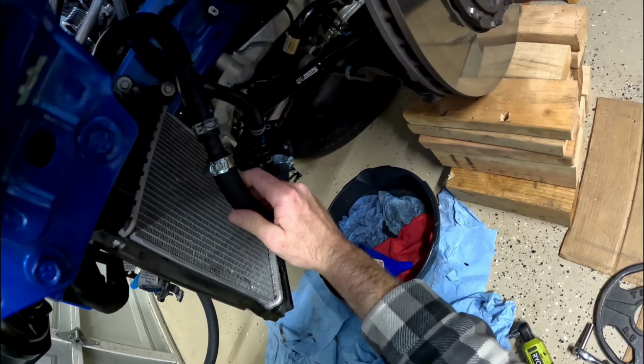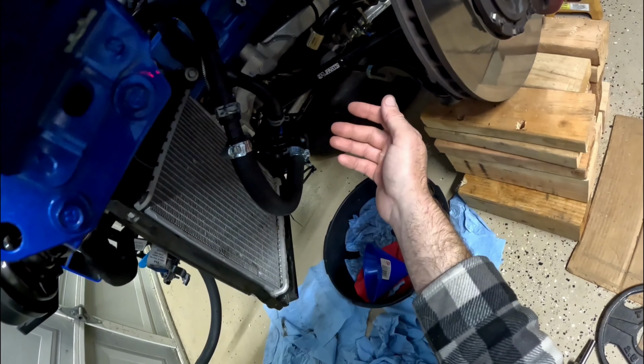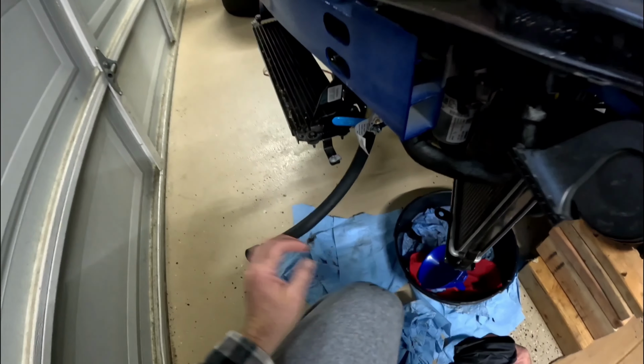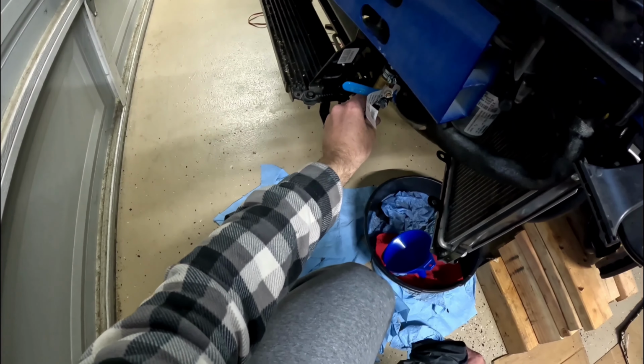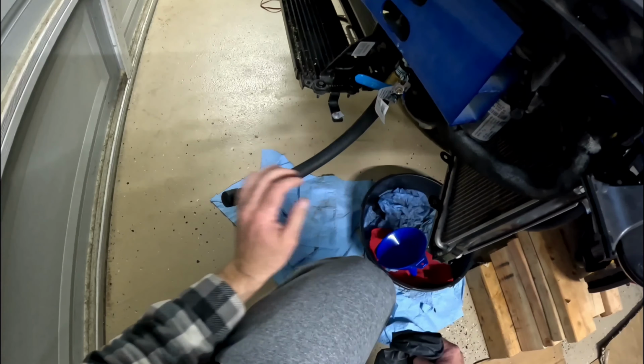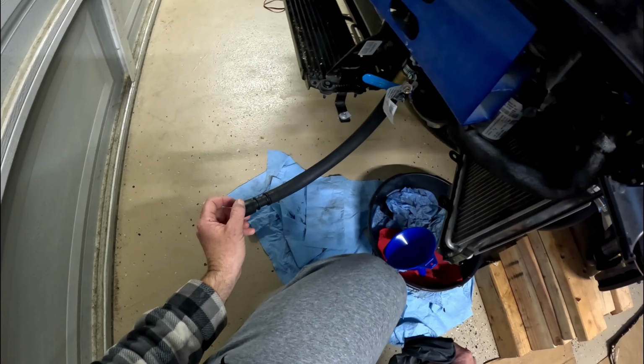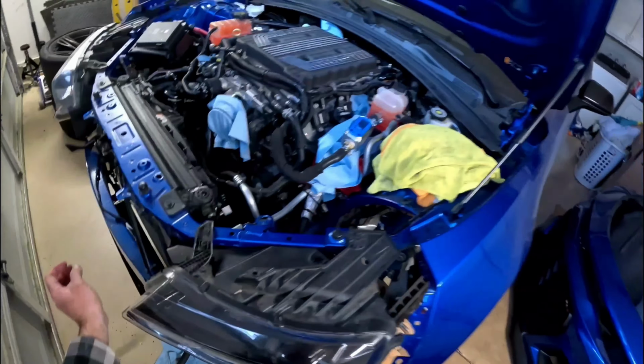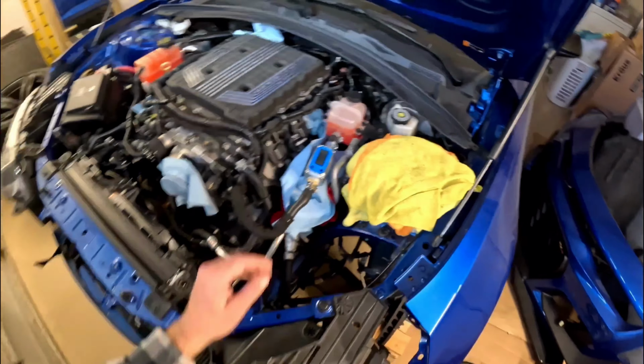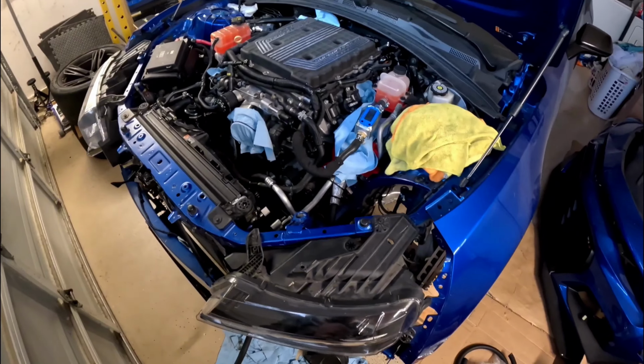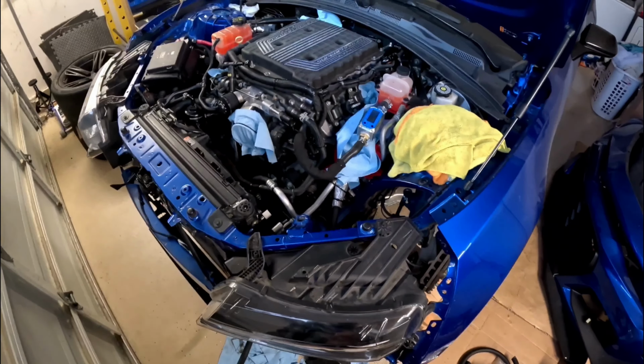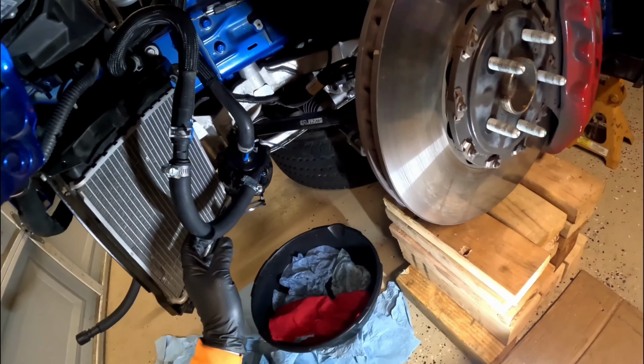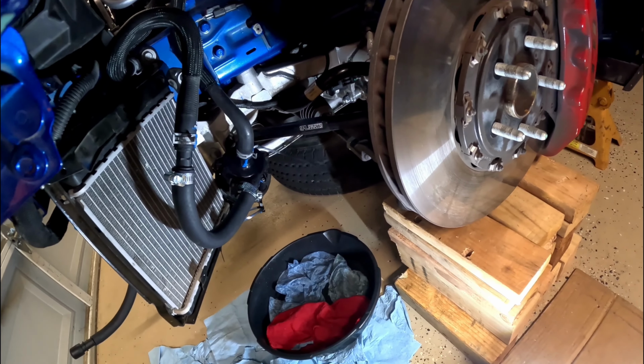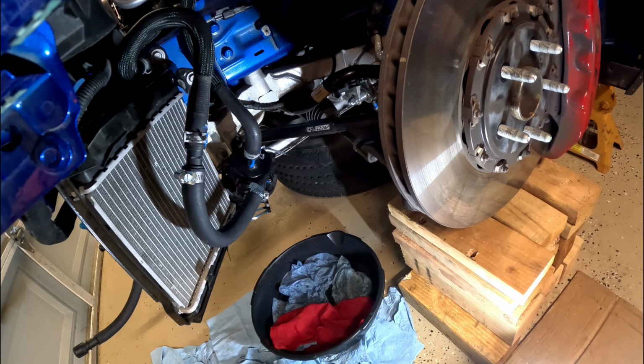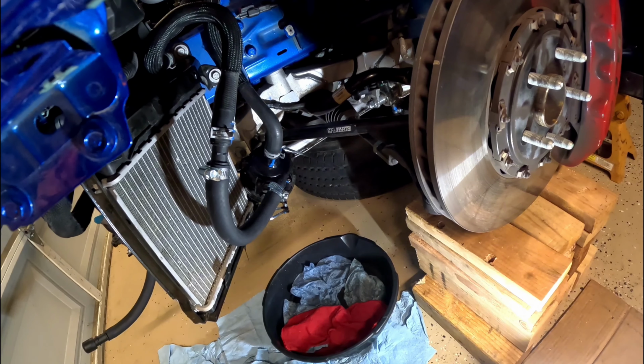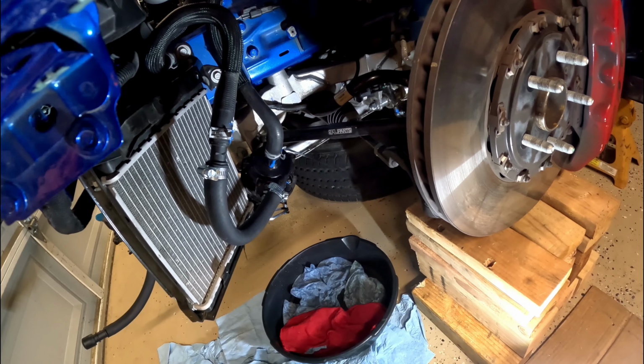Now there could also be some kind of blockage in the system itself. What I would like to do is go ahead and bypass the main heat exchanger as well as the supercharger and just test the pump going to the small heat exchanger and then back up to the reservoir and see what kind of flow number that's going to give us, and we can see how much of a restriction the rest of the system is. I'll go ahead and get some new hoses run from the small heat exchanger up to the reservoir and we can keep pretty much everything else in place.